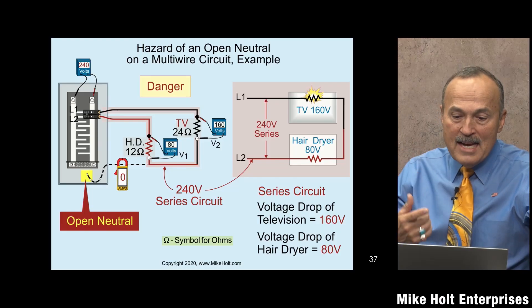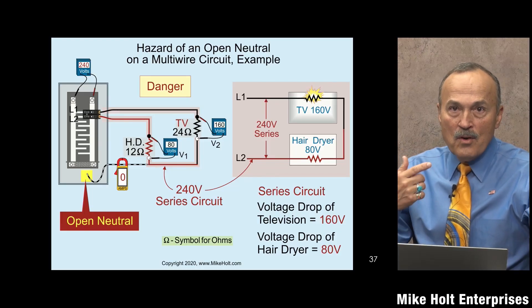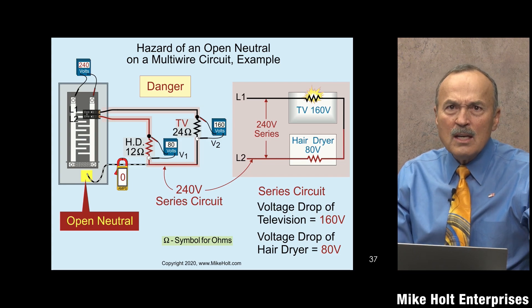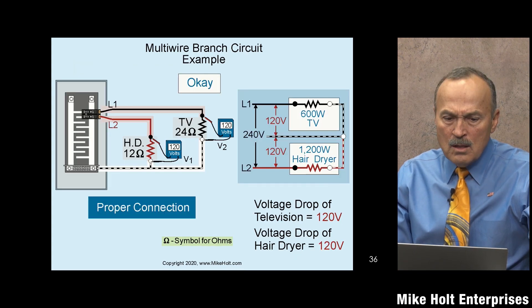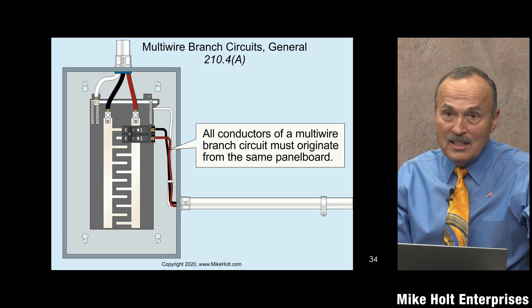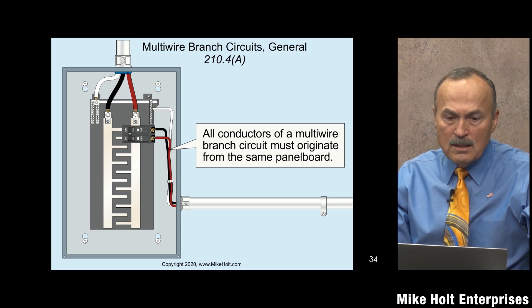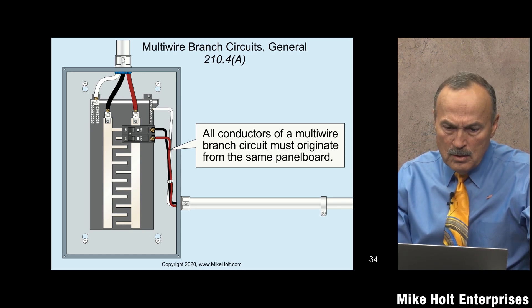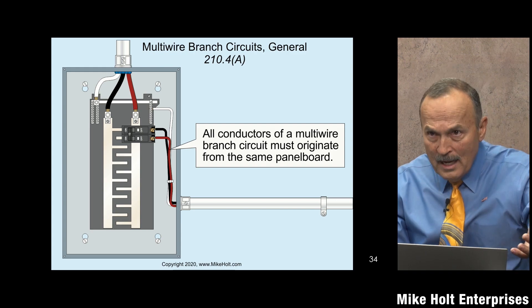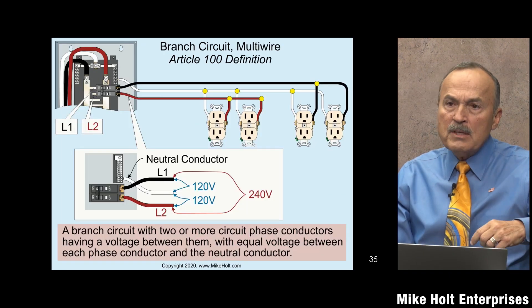Eric points out that this is exactly why you're only allowed to put one neutral under a screw — we'll cover that. Understanding this concept is the foundation for following the code. The multi-wire branch circuit, also known as the Edison circuit, is permitted by code.